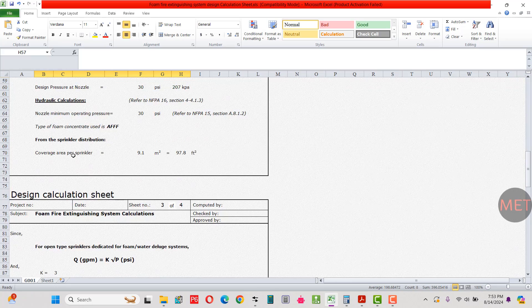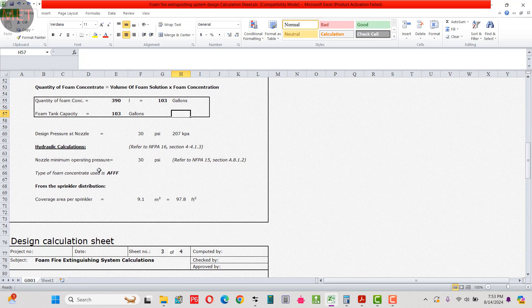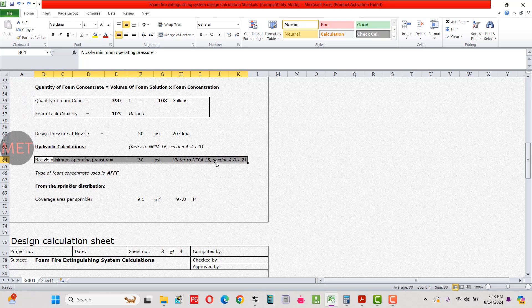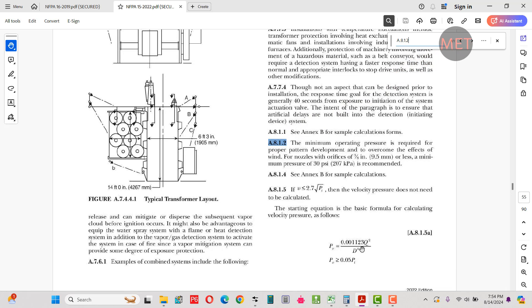Next is design pressure at the nozzle. The minimum operating pressure for the nozzle is 30 psi as per NFPA 15 section A.8.1.2. That section states: the minimum operating pressure required for proper pattern development and to overcome the effect of wind, for nozzles with an orifice of 3/8 inch (9.5 mm) or less, is 30 psi, equivalent to 207 kPa. We've taken 30 psi here.